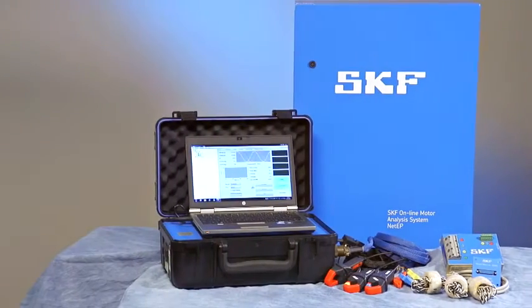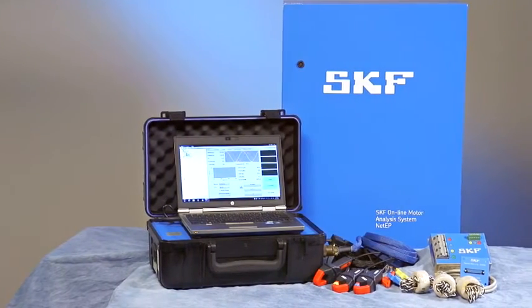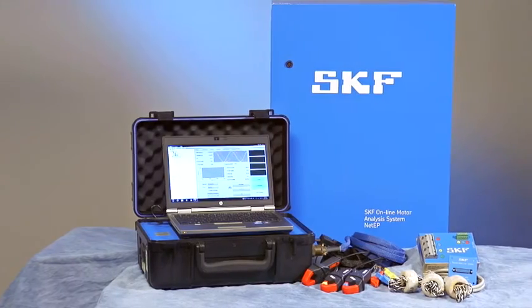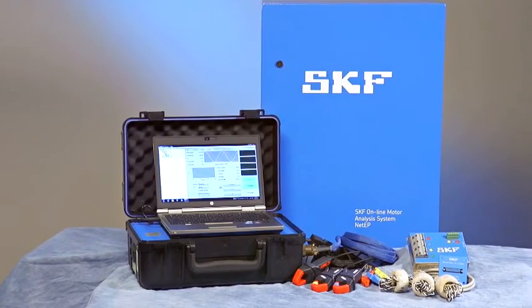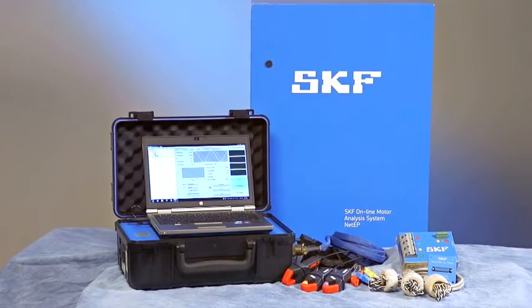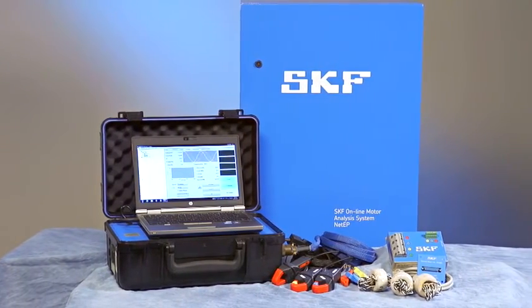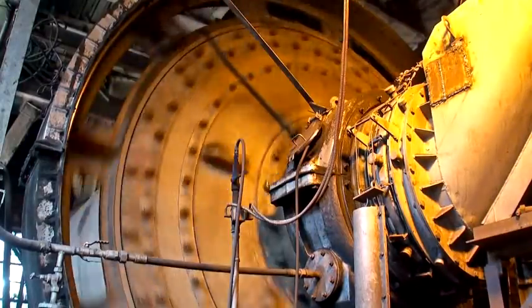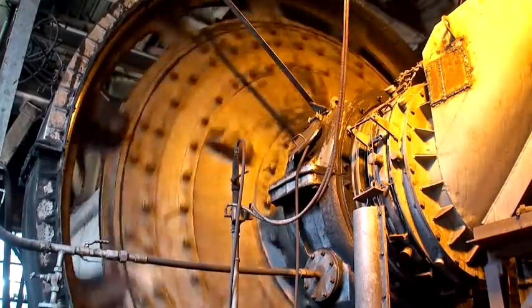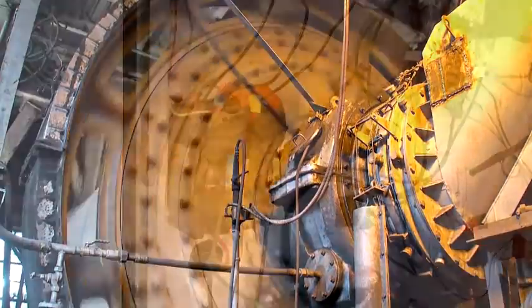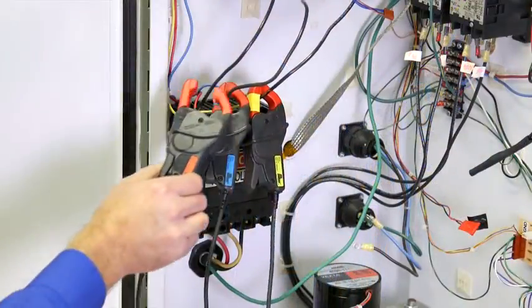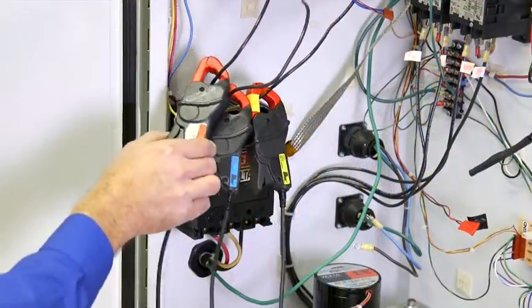Now let's look at the motor operating point using SKF dynamic motor analyzers. The operating point is measured while the motor or machine is energized and operating. Connections are made to measure the motor voltages and currents.